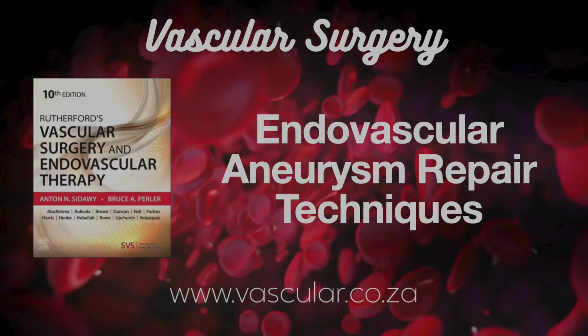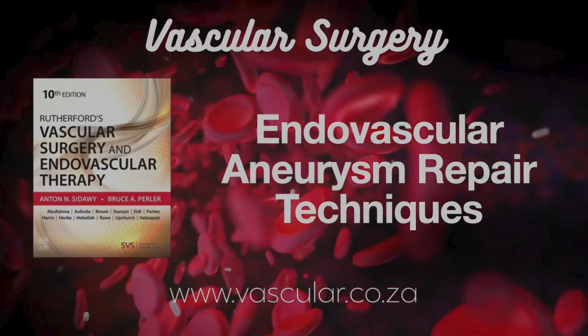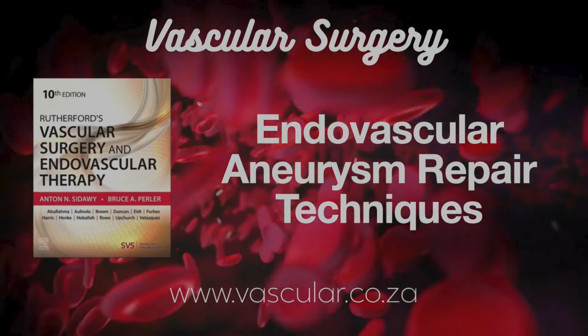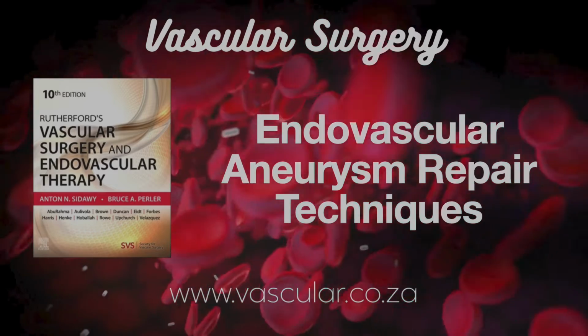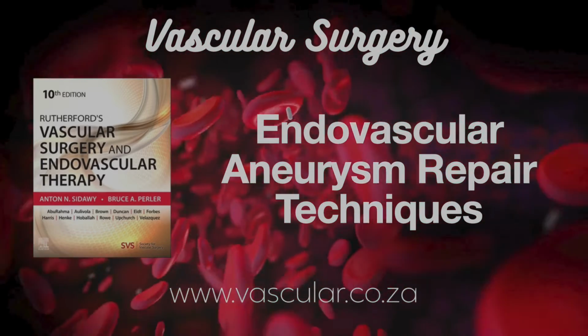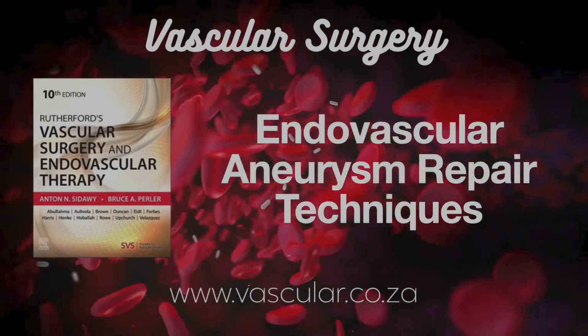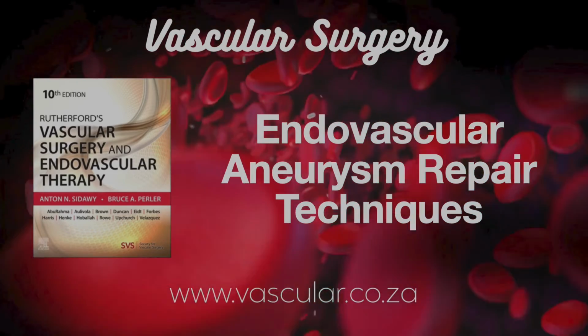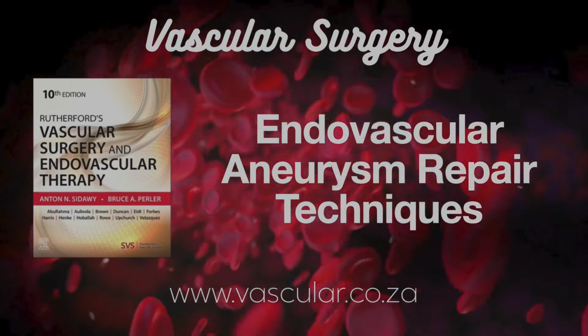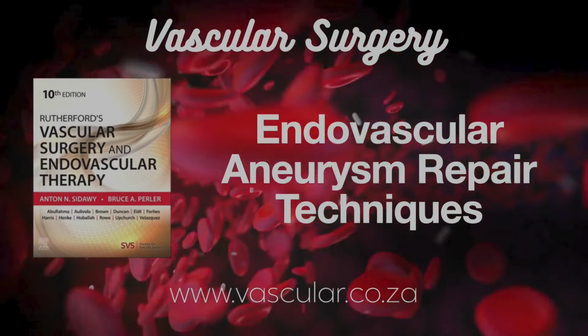Endurant with endo anchors can go shorter, down to 4 millimeter. Aorfix can handle angles up to 90 degrees. Max neck diameter is usually around 32 millimeter. And the ideal shape? Ideally, parallel sides, no big clots stuck to the wall, no heavy calcium. Irregular shapes, conical, reverse conical, double bubble bulges, have a higher risk of seal problems, endo leaks.